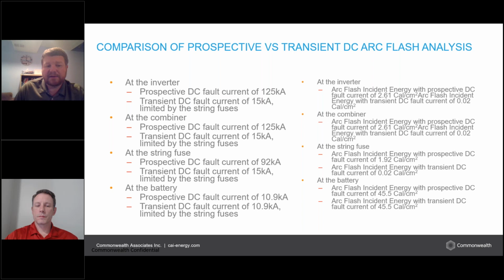What we can see though is even though we were able to highly mitigate the DC arc flash in a number of areas, that also implies that we have protection in fuses in those areas. What we do see at the bottom here is that at the top of the battery stack, like Chris mentioned earlier, there are no protective devices to clear faults. The DC transient analysis does us no good because there isn't a protective device to clear the fault. Therefore, we're stuck using the IEEE 1584 maximum clearing time, which right now is 2 seconds.